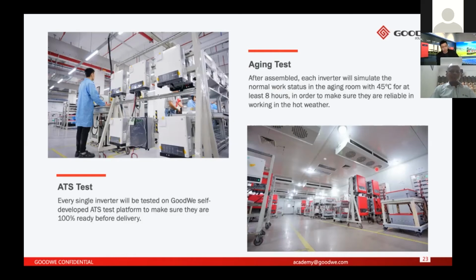Okay, so this is a cabinet simulating 45 degrees centigrade. The inverters will be put there to work at full load with a simulated DC source for at least 8 hours, to make sure they can work perfectly in the high temperature environment, which is also a requirement from your country as well.